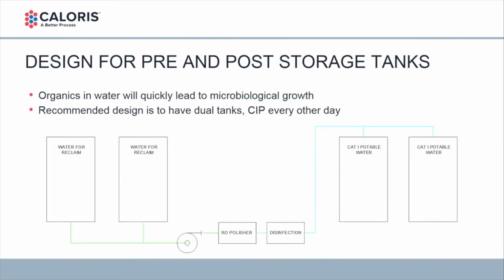Okay, how do we design for pre and post storage of the tanks for the polisher? So, like I've been talking about, we need to really look at the organics closely in this water. If we have organics in the water, they're going to quickly lead to microbiological growth downstream, and you'll even have the same growth upstream too.